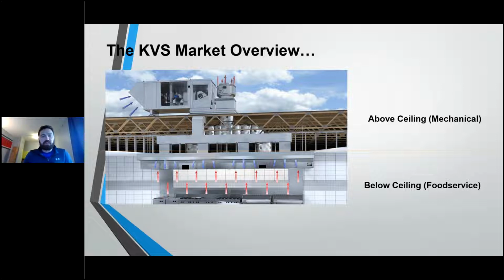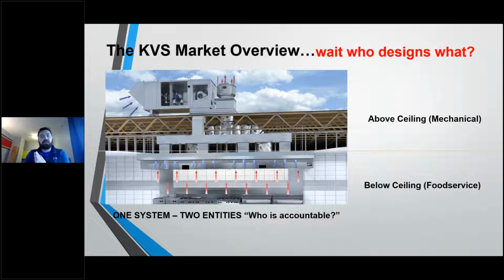What that means is that across the country, we have a split market in one system. Ultimately, the biggest issue we see nationwide when this gets to site is: wait, who designs what? We're coming in and seeing a lot of one system, two entities. So who is accountable when something goes wrong? One of the most commonly missed items in the scope of a kitchen ventilation design is the controls, because the above-ceiling contractor or designer thinks that's part of the below ceiling and vice versa. And then the controls that are required per code are not specified in that scope.